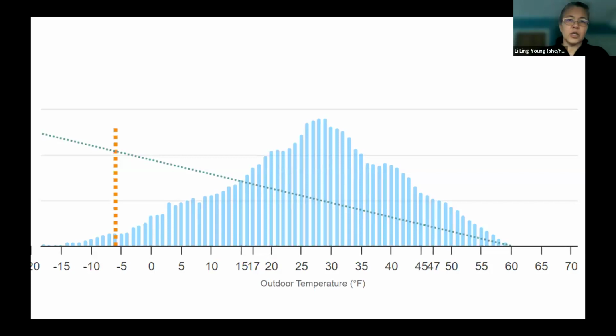The other thing this chart shows is the orange vertical dotted line, which is the design temperature. So where the slope of the load intersects the design temperature, that's the design load for this building.